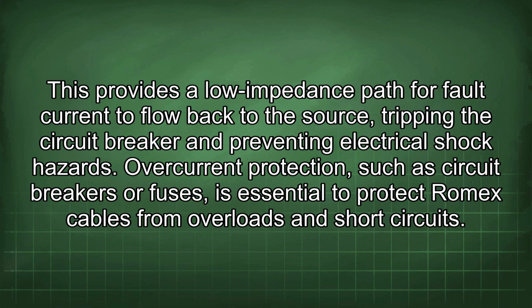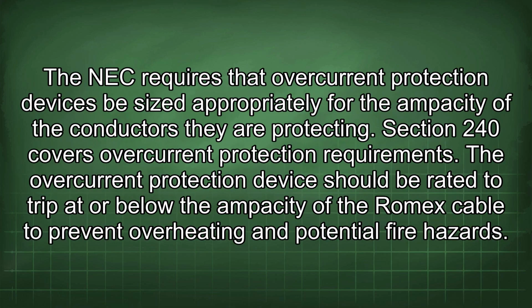preventing electrical shock hazards. Overcurrent protection, such as circuit breakers or fuses, is essential to protect Romex cables from overloads and short circuits. The NEC requires that overcurrent protection devices be sized appropriately for the ampacity of the conductors they are protecting. Section 240 covers overcurrent protection requirements. The overcurrent protection device should be rated to trip at or below the ampacity of the Romex cable to prevent overheating and potential fire hazards.